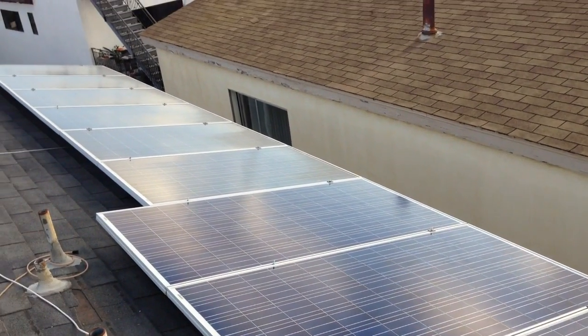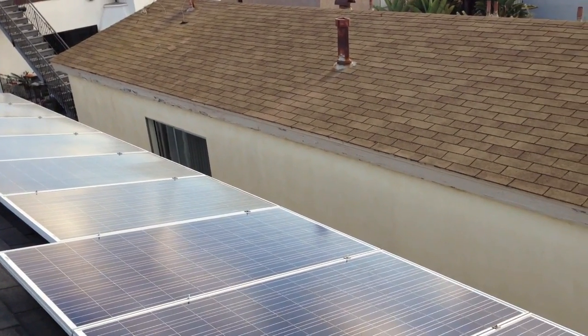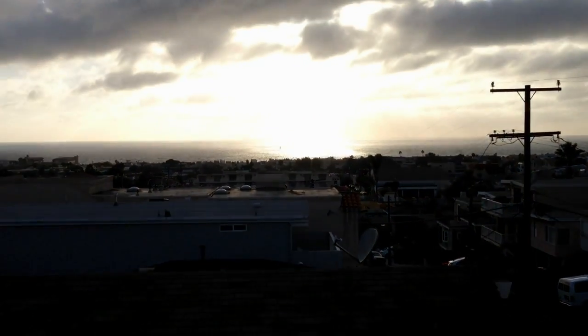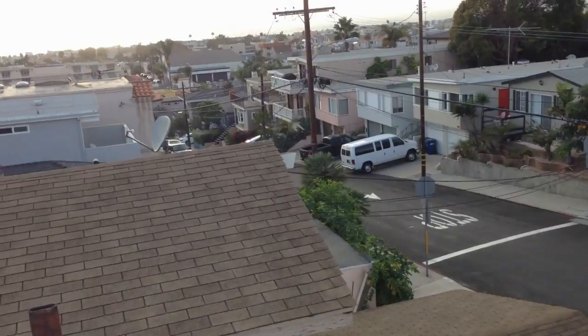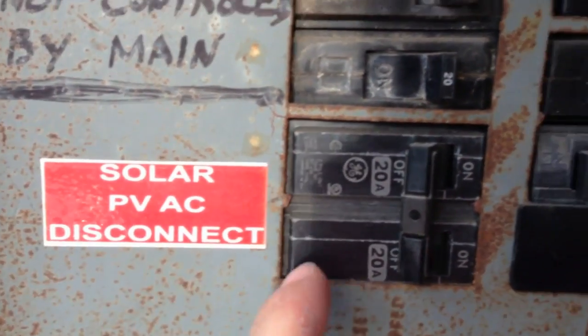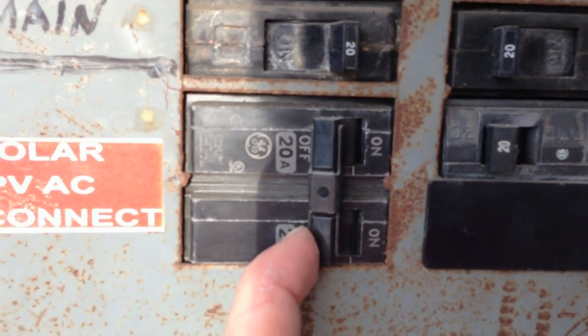Now I'm just going to click on my 2-pole 20-amp breaker. A little sunset action — fire them up. There's not much sun, so we'll see. Going to our breaker, turn back on our double amp. By the way, this is my only disconnect — I don't have one on the roof. And by the way, that's all you need for code. Some cities might want more, but not mine.